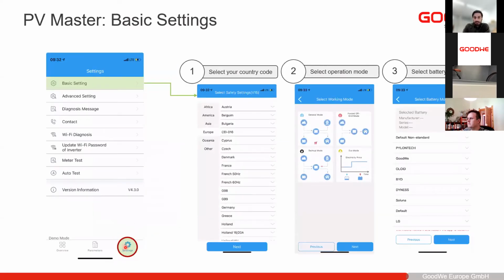If you click on settings, the commissioning of the hybrid inverters is actually, in my opinion, easier than the commissioning of the on-grid inverter, because PV Master will guide you through the whole setup. For the inverter to work, you only need to click here on basic settings, and then it will guide you through everything you need to select in order for the inverter to be connected.